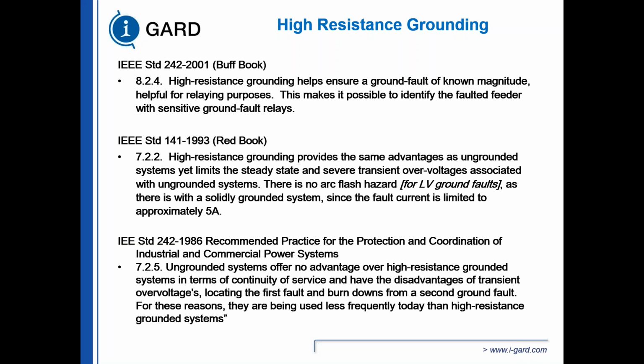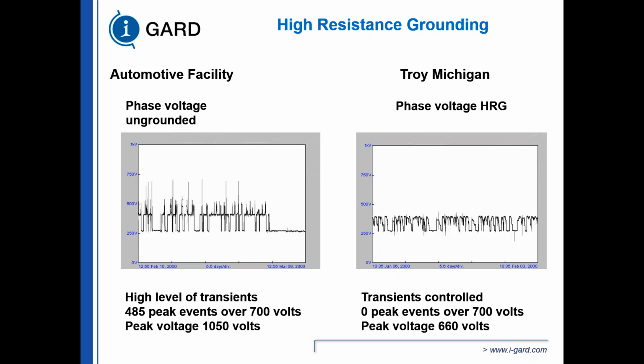High resistance grounding provides the same advantages as ungrounded, meaning that you don't have to isolate, except you don't have the disadvantage of escalating overvoltages. And ungrounded systems offer no advantages over high resistance grounded systems in terms of service continuity.